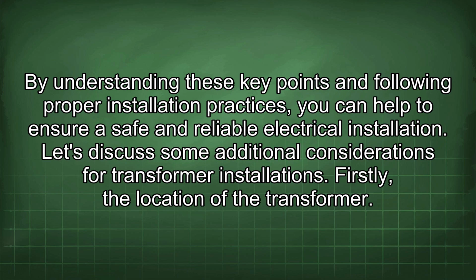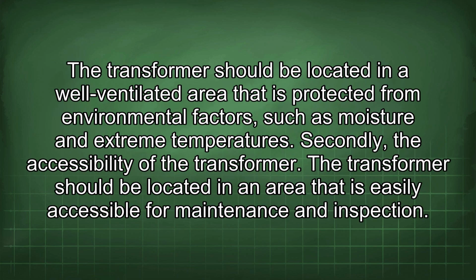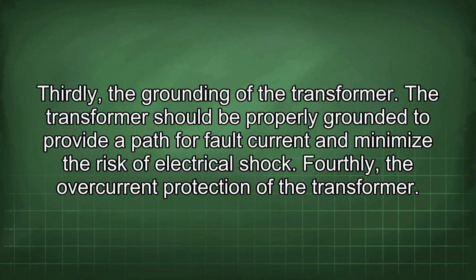Firstly, the location of the transformer. The transformer should be located in a well-ventilated area that is protected from environmental factors such as moisture and extreme temperatures. Secondly, the accessibility of the transformer. The transformer should be located in an area that is easily accessible for maintenance and inspection. Thirdly, the grounding of the transformer. The transformer should be properly grounded to provide a path for fault current and minimize the risk of electrical shock.